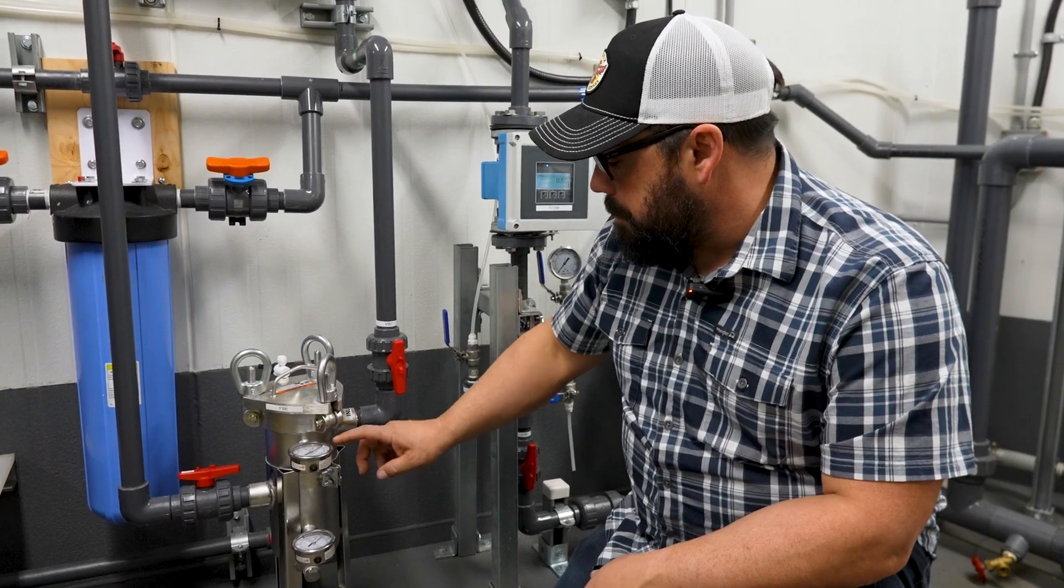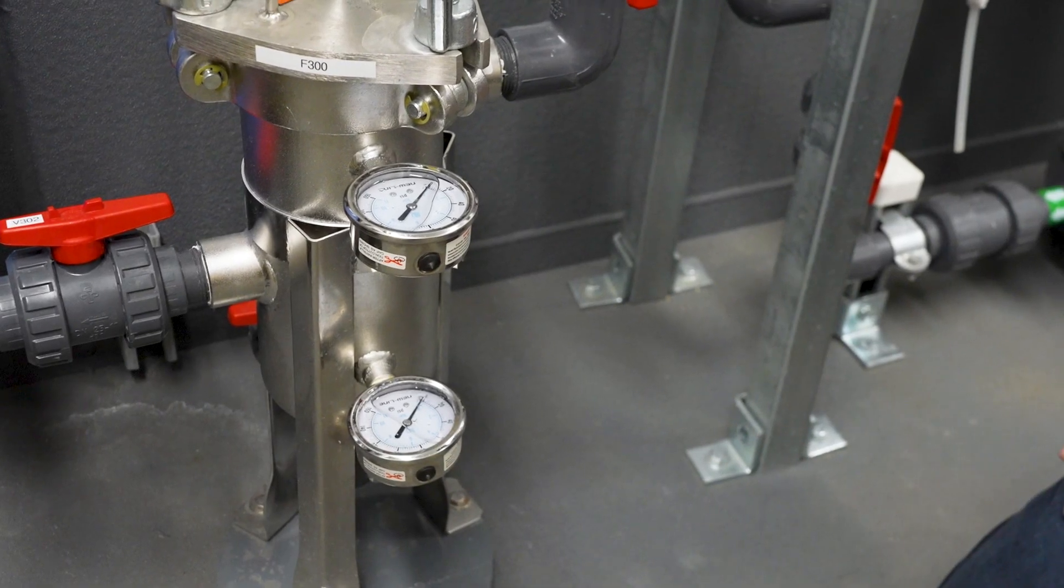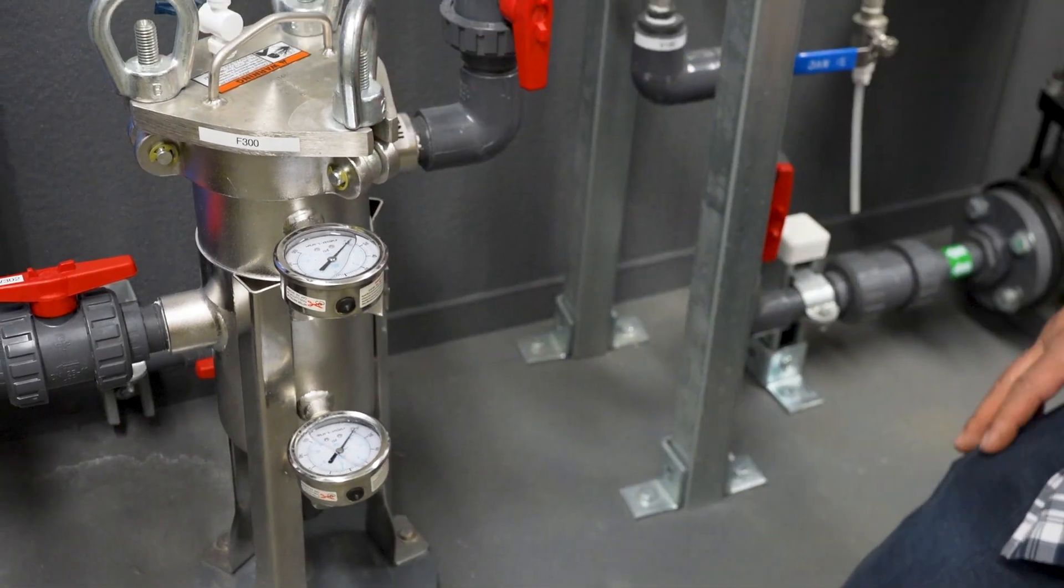They have gauges on them. This is your inlet gauge of pressure. This is your outlet pressure and you do the monitoring between 10 to 15 psi. You'll know it's time to change your bag.